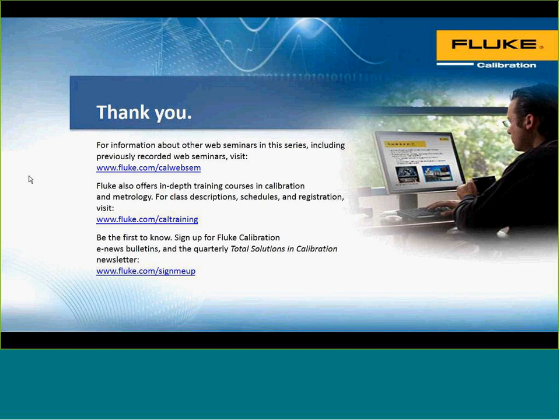There's another, more specific question, similar to a previous one. On the 7615, one of our hydraulic controllers capable up to 40,000 psi, can it use fluids other than the HT230? If your instrument is manufactured with a certain fluid, its control algorithm could be tailored for the density of that fluid.